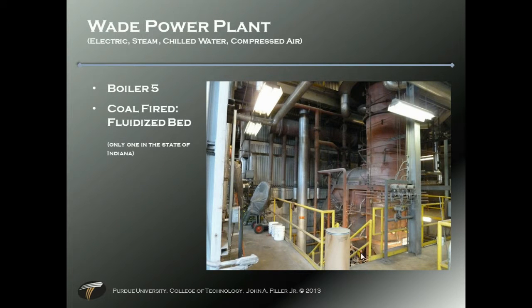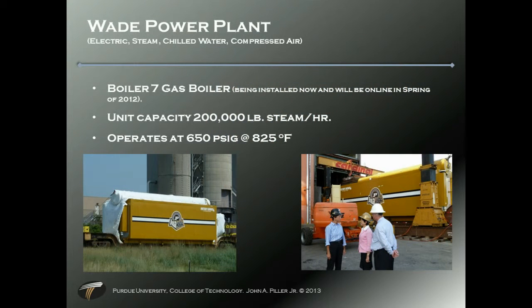Boiler number 5. This is a very interesting boiler. It's the only one in the state of Indiana. It's called a fluidized bed. Let's hit its specs real quick. Again, 200,000 pounds of steam per hour. Reaches the 650 psig. That's the header of the entire system. 810 degrees Fahrenheit. It takes crushed, air-swept coal stoked. We'll talk about what that means in a second.